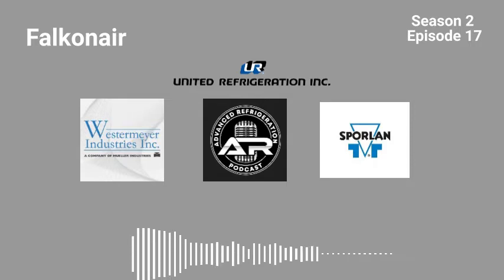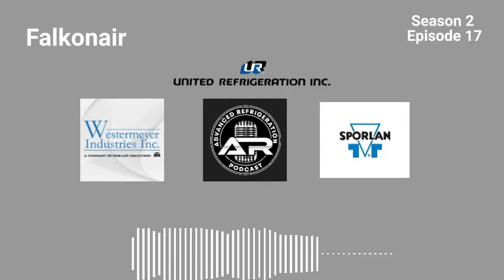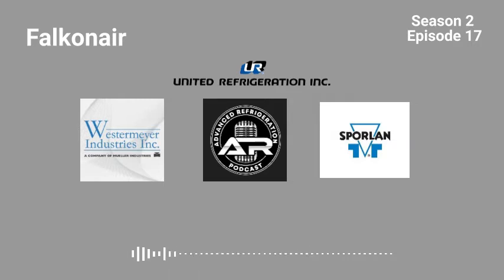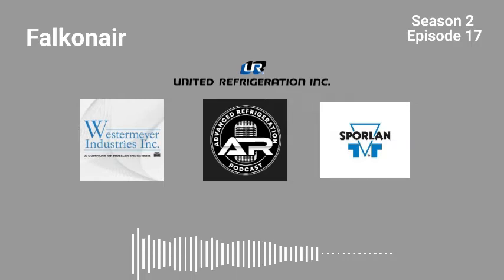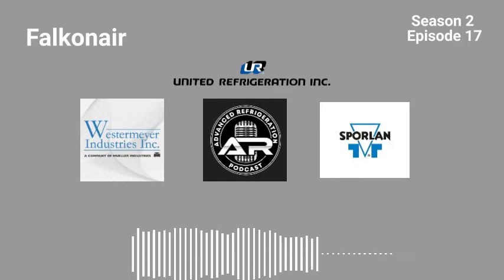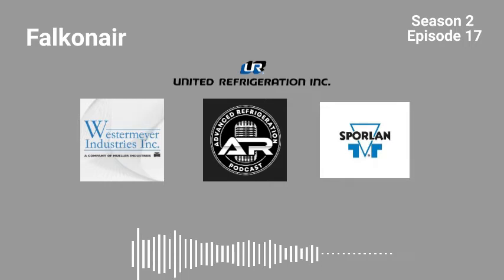Because the algorithm is going to go off of what you are presenting it with. So I'm still confused. I'm still thoroughly confused. I'm trying to wrap my head around this. I don't understand how, by the discharge and the suction temperature, because that's what you guys are monitoring, correct? Correct. How you're controlling the capacity of that rack to maintain a certain suction pressure in order to maintain a certain saturation for the rack to actually function properly, if your smart controllers are basically taking the place of the energy management system, is really what it sounds like. It sounds like they're their own compressor control.